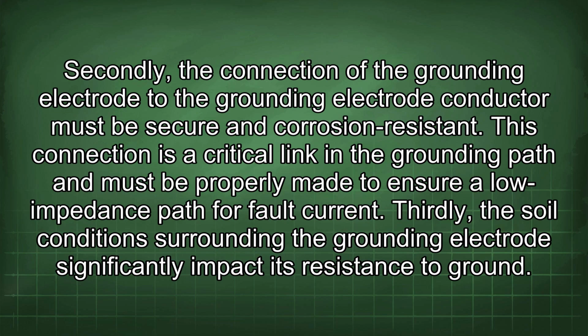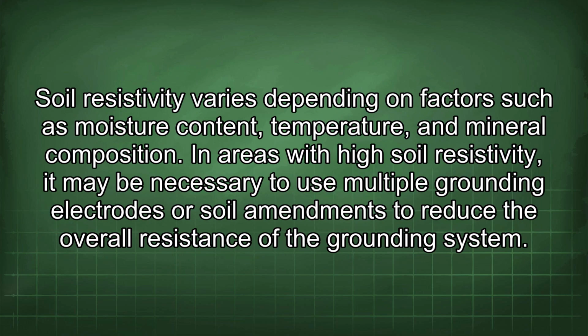Secondly, the connection of the grounding electrode to the grounding electrode conductor must be secure and corrosion resistant. This connection is a critical link in the grounding path and must be properly made to ensure a low impedance path for fault current. Thirdly, the soil conditions surrounding the grounding electrode significantly impact its resistance to ground. Soil resistivity varies depending on factors such as moisture content, temperature, and mineral composition. In areas with high soil resistivity, it may be necessary to use multiple grounding electrodes or soil amendments to reduce the overall resistance of the grounding system.